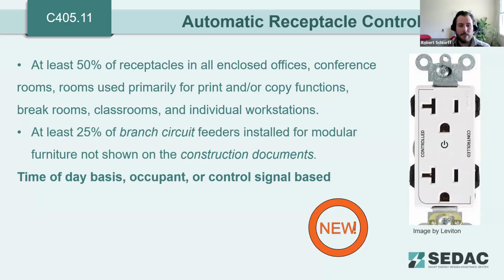These small appliances can add up to some fairly significant plug loads for a building, and the code is trying to address those plug loads by including some requirements for automatic receptacles. You can control these automatic receptacles on a time of day basis, an occupant basis, so potentially occupant sensors or some sort of security badge system at the entrance to the building, or on a control signal basis. These receptacles must be permanently marked as controlled, as you can see there in the image.